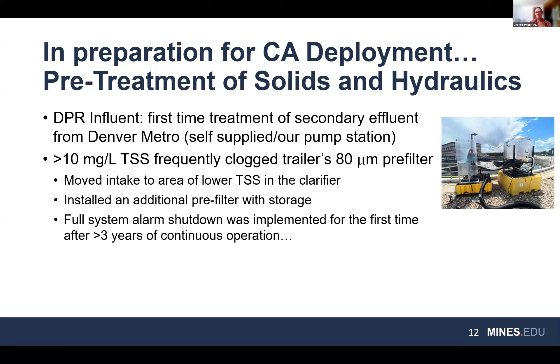To overcome this issue, we installed an additional pre-filter followed by a storage tank to make sure that when these filters backwash themselves, we're not sacrificing the pressure needed to continue operation. This was also the first time in 3 years of continuous operation that we found benefit in installing an alarm for system shutdown in the event of a severe clog impacting flow or any other issue affecting continuous operation.